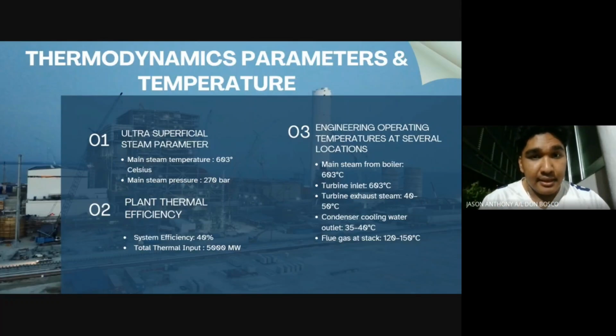It is not stated anywhere, but we use the formula: efficiency is equal to the output over the input. As we know, the output is 2000 megawatt by TNB, and the 40 percent is also mentioned in many news reports and by TNB. As for the engineering operating system, we have the main steam boilers at 603 degrees Celsius. After leaving the boiler, the steam goes through the turbine, and the steam temperature decreases significantly before entering the condenser. The condenser is about 35 to 40 degrees Celsius, and then the flue gas stack is approximately 120 to 150 degrees Celsius. Next slide.